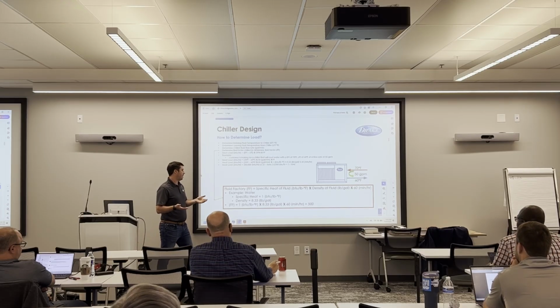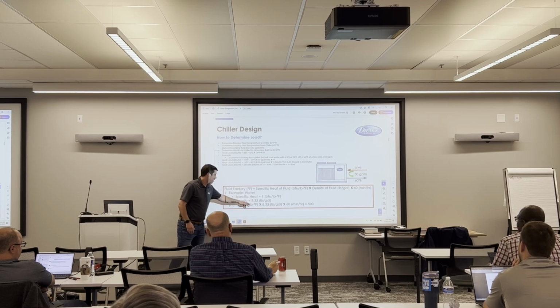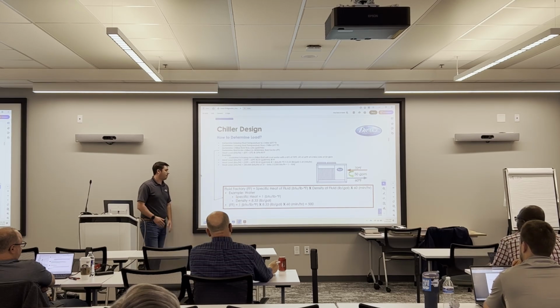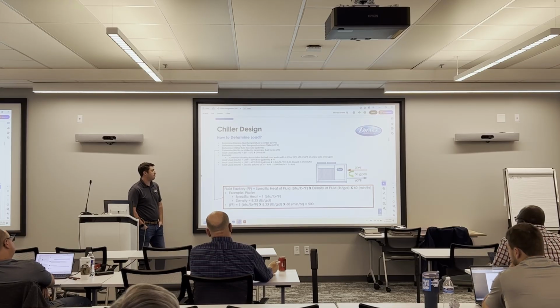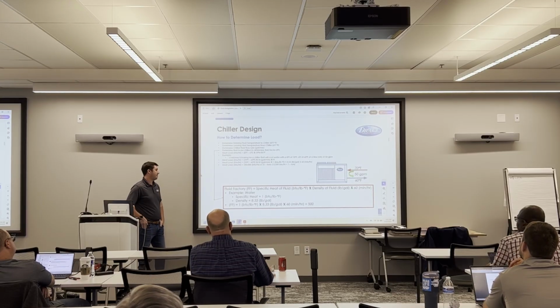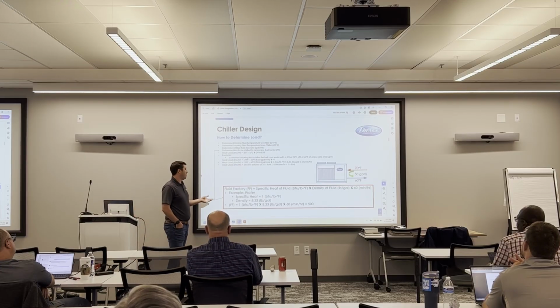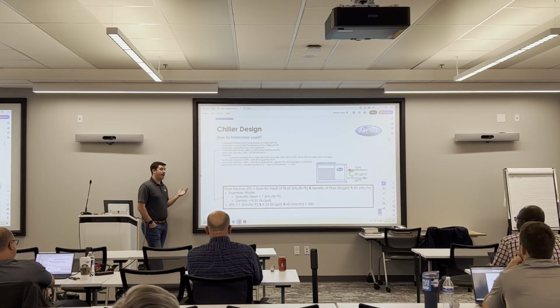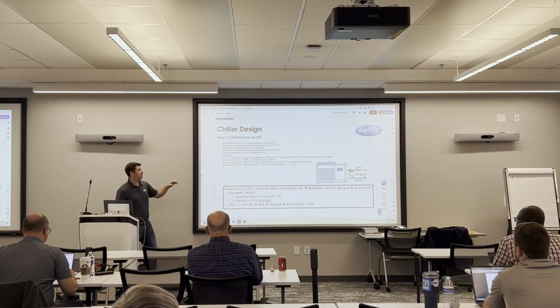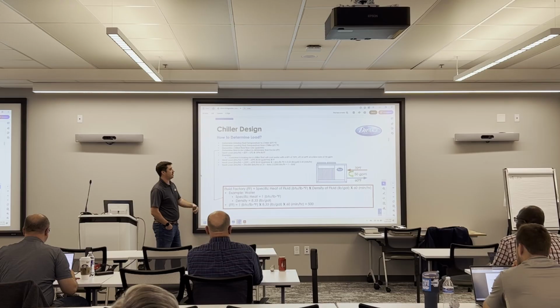So if they say it's a 100-gallon tank, I know that's about 833 pounds, roughly. So it's going to take about 833 BTUs to move that tank 1 degree. But they want to move it 10 degrees, so we multiply that by 10. It's about 8,300 BTUs. And if they say they want to do it in an hour, I need a chiller that can do 8,300 BTUs per hour. If they wanted to do it in a half hour, I multiply that value by 2. And if they want to do it in 2 hours, I can divide that number by 2.